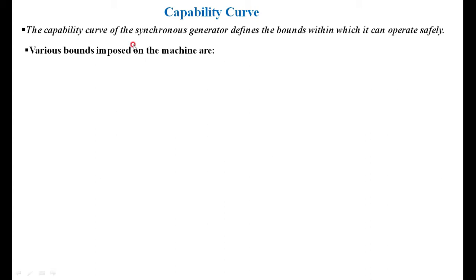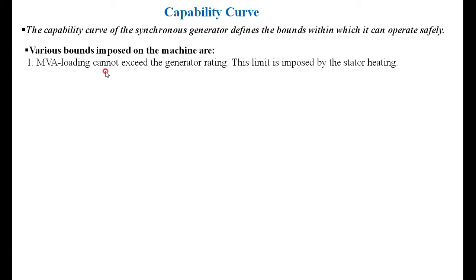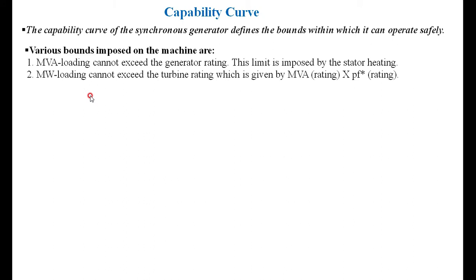The first limitation is that MVA loading cannot exceed the generator rating. That is, one should not load the generator beyond its MVA rating. You should not exceed the MVA rating of the generator within which you are operating the synchronous generator.